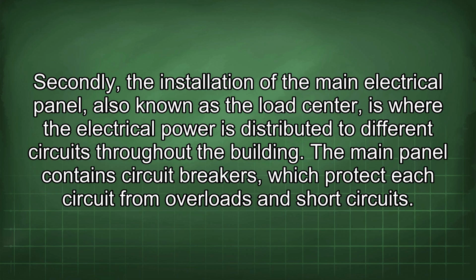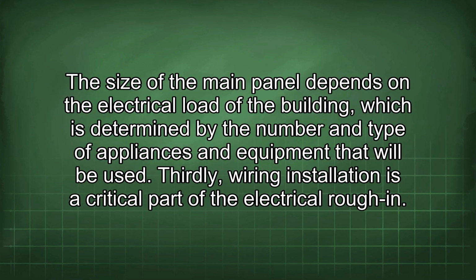Secondly, the installation of the main electrical panel, also known as the load center, is where the electrical power is distributed to different circuits throughout the building. The main panel contains circuit breakers, which protect each circuit from overload and short circuits. The size of the main panel depends on the electrical load of the building, which is determined by the number and type of appliances and equipment that will be used.